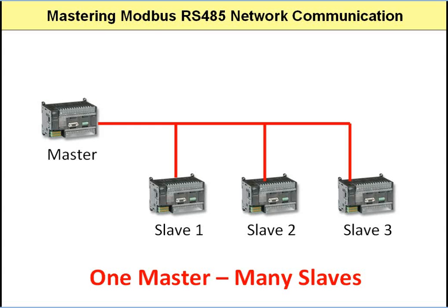A slave never initiates a conversation. So 100% of all the conversations happening on a Modbus network happen because the Modbus master initiated it. Furthermore, once a device is configured as the master on the network, it stays as the master. No other device can temporarily become the master on the network. They will always be Modbus slaves.